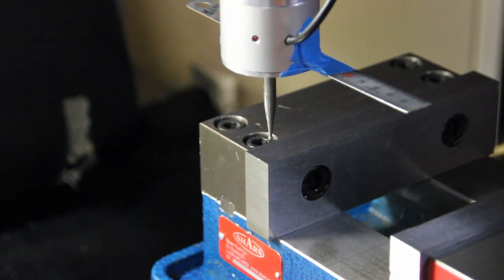Okay, so now we're going to do a probe down move. I've already done one, and it set the zero to zero. Now I'm going to do another one here, turning the auto zero off, and we'll see on the screen in a minute what the repeatability is. Every time I do it, it should give me a number relatively close to zero as to where the probe stops.